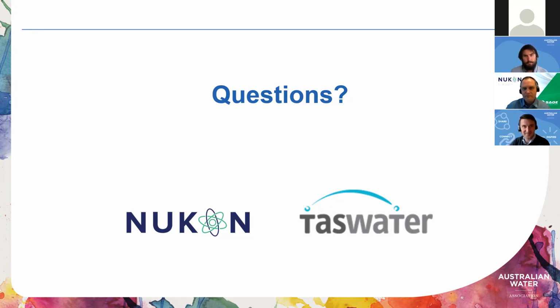Great, thanks Andrew. We've got a question here also from Chris, who says the envelope looks quite dynamic and changeable - could you speak to that? Absolutely, this is one of the key features that actually sets it apart from traditional automation approaches. The operating conditions, in this case, we're looking at a dynamic bound - we only care about the upper bound here, so if the time between pump runs goes too long than we expect. But the software is capable of having an upper and lower bound. If you have a process that needs to be within very tight tolerances all the time, we can create what's called a reference profile for that, which creates an operating envelope with an upper and lower bound that can be dynamic as well.